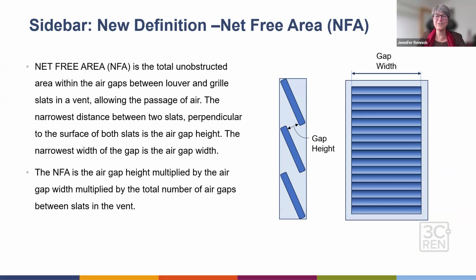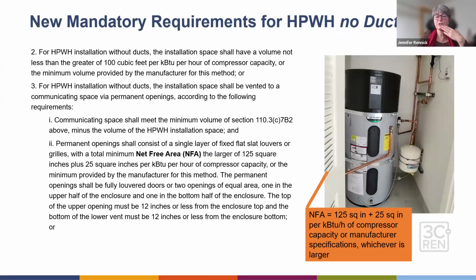Hopefully you would be able to look this up, maybe through the manufacturer of your door, or somehow verify that you're going to meet this net free area. It's basically the gap height and the gap width times how many slats you have, in inches. Then you would know if you're going to meet that 125 square inches plus another 25 square inches per kBTU per hour of compressor capacity.